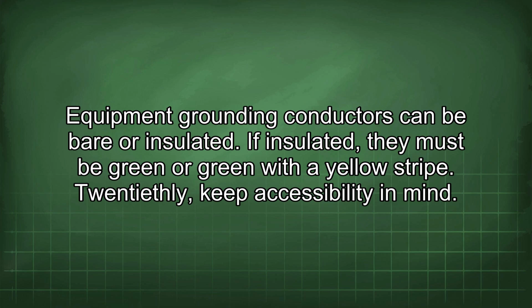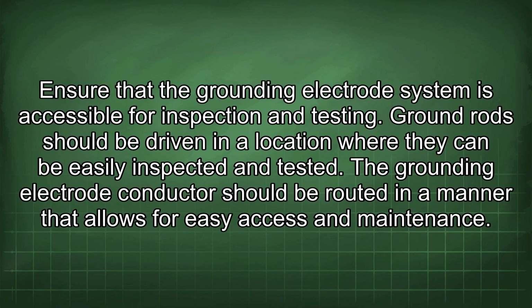20thly, keep accessibility in mind. Ensure that the grounding electrode system is accessible for inspection and testing. Ground rods should be driven in a location where they can be easily inspected and tested. The grounding electrode conductor should be routed in a manner that allows for easy access and maintenance.